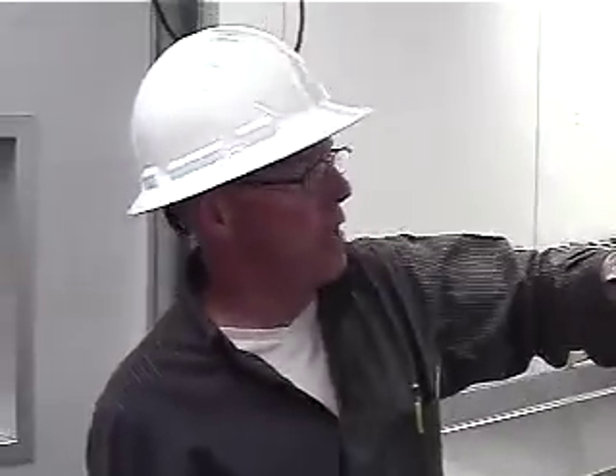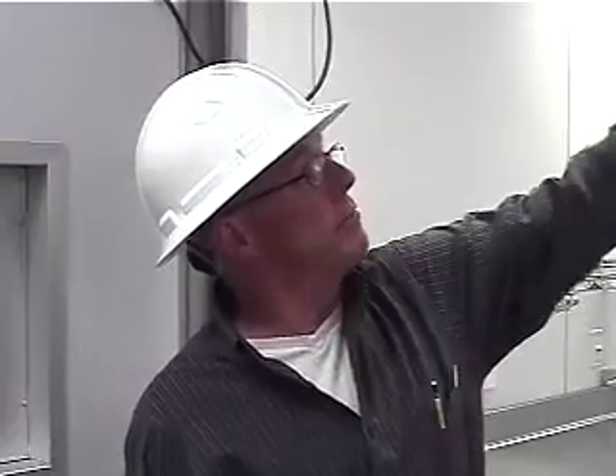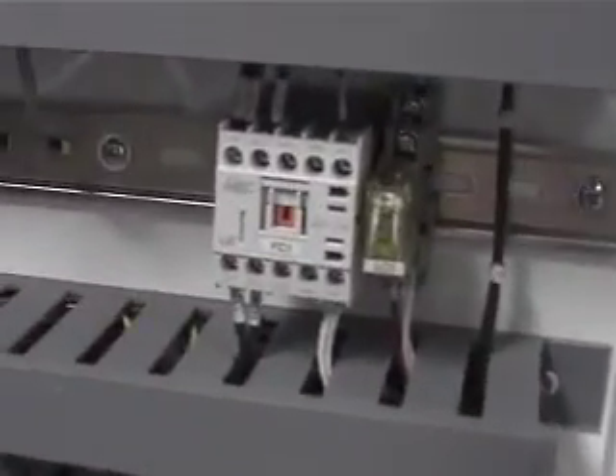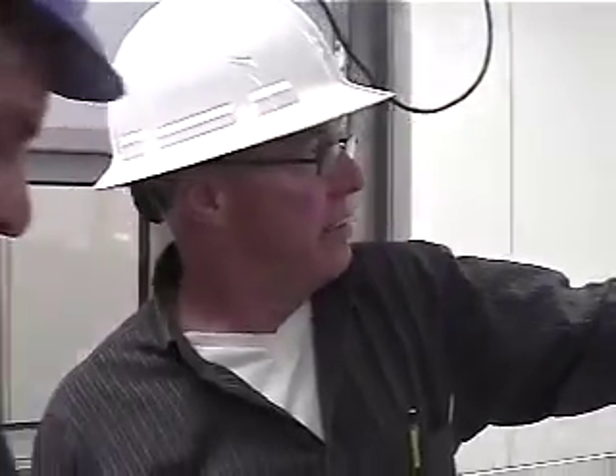One thing I failed to mention, the door heat. One of the problems we had early on was the door heat. You can feel the door heat around here. You leave the power to it, but the door heat would get too hot just because there's no cooling going on on the inside. We actually run the door heat circuit across the fan contactor. That's what this guy here is. So if the fans aren't working, it kills the door heat. So if you're trying to troubleshoot the door heat with the fans off, you're going to have problems. It's just you want a little warmth there.